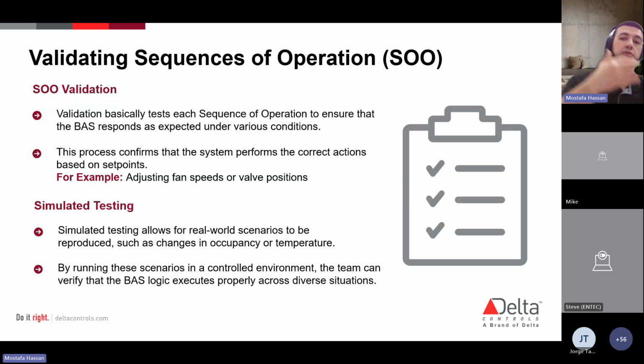We also want to go back to your sequence of operations and validate all the sequences, make sure the control logic makes sense, and make sure you have what the owner, the customer, actually requested. They want control of these specific parts of the building. And you as a consultant are telling them, listen, you should probably include these sections. We probably want to monitor this. Maybe you want to avoid Local Law 97 fines and things like that. Those are all steps. Those are all necessary, right? And you can achieve that through a proper sequence of operation.